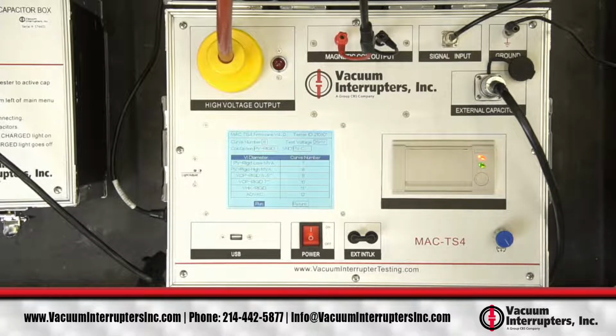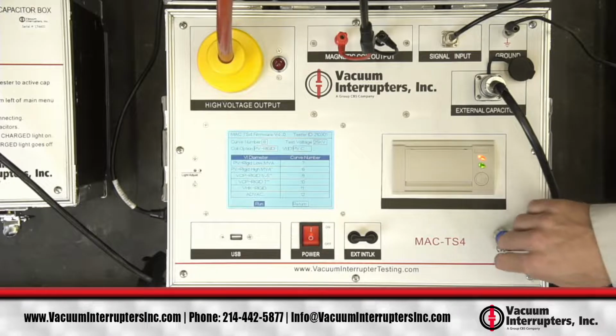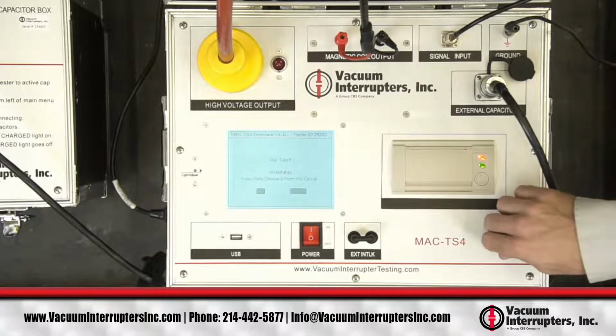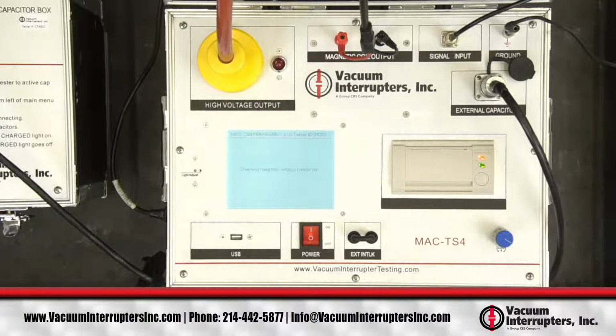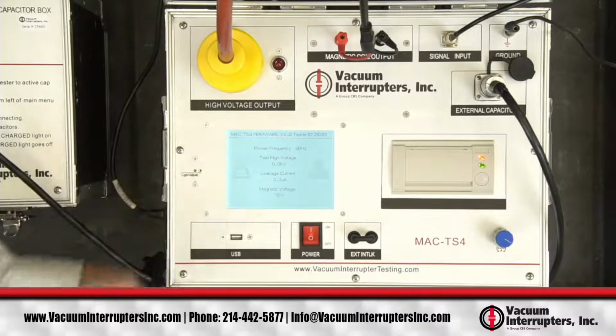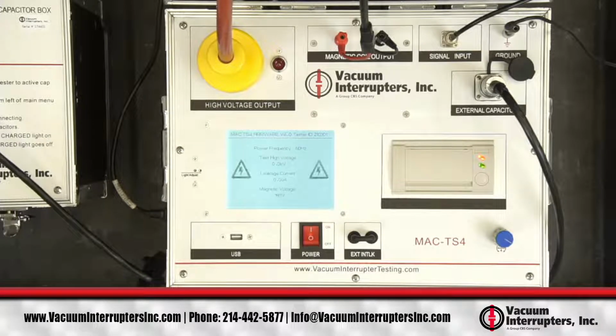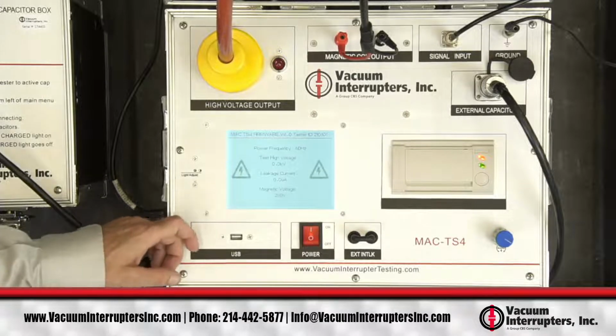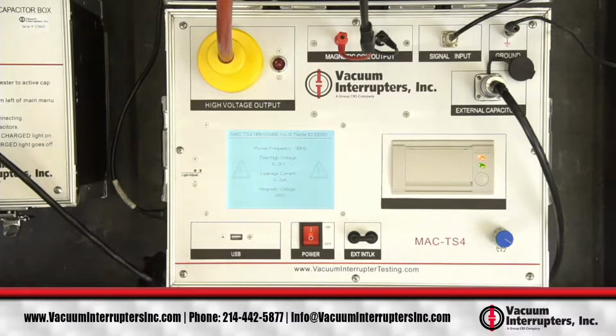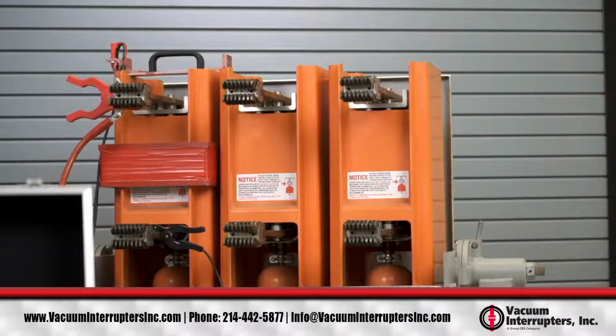So this test takes just slightly longer because we have to charge the extra capacitors inside of the external capacitor box. So we're going to run through this test the same. So we're applying the 25 kV. Very low leakage current, like we would expect. So again, this is going to take a little bit longer. When it gets to 350 volts, it will accelerate. So we're going to 700 volts.